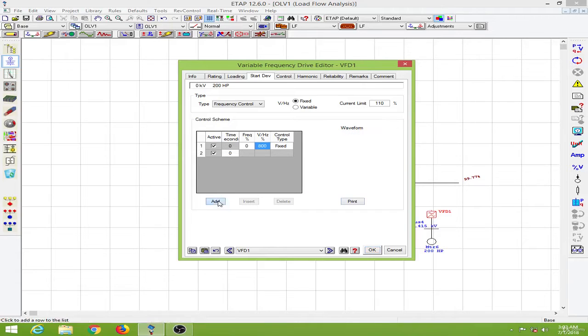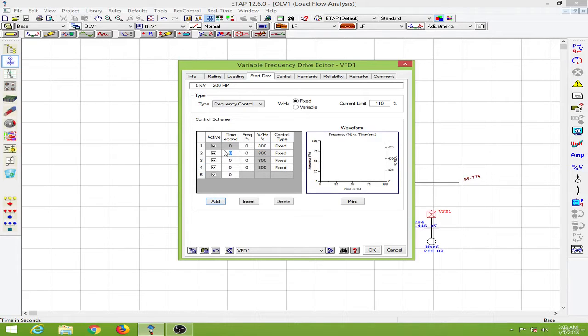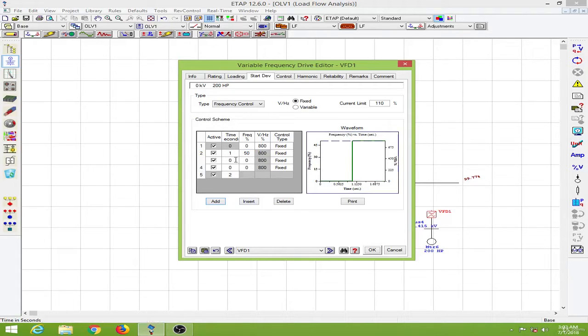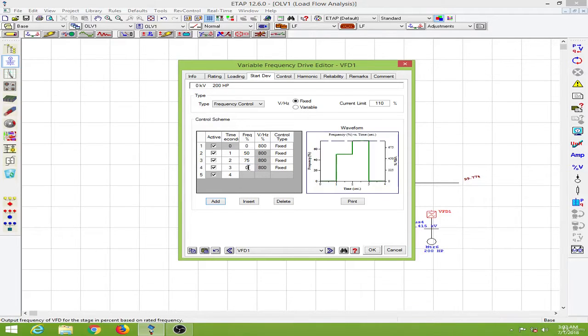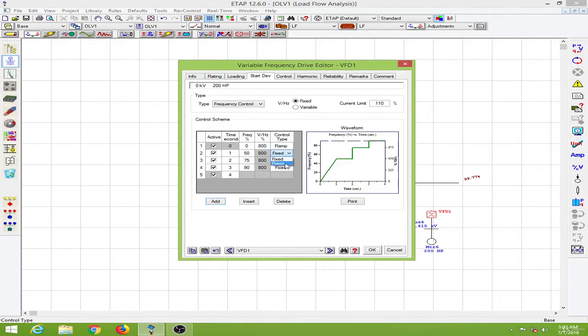Now I will add in more points. At the first second I will have about 50 percent of my frequency, at the second second I will have 75 percent, and at the third second I will have 90 percent of my frequency. I will change this to ramp because I want a smooth transition from 50 to 75 and so on, giving us a smooth slope that varies the frequency with time.